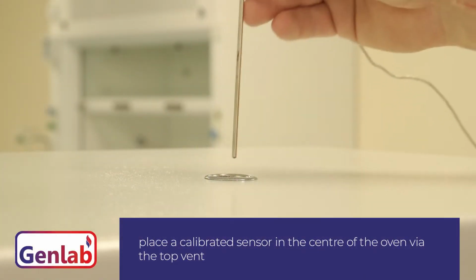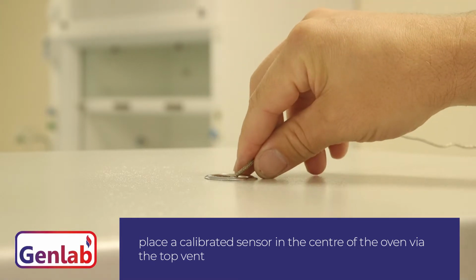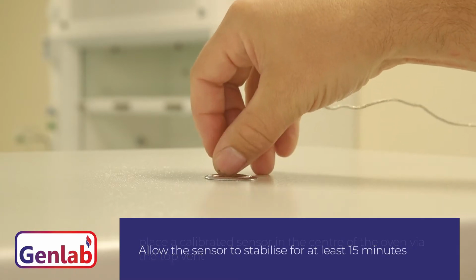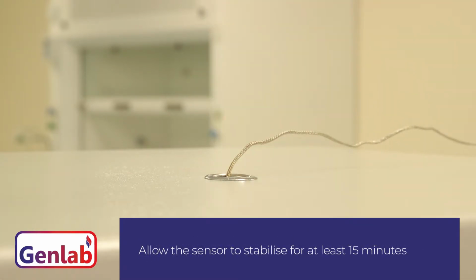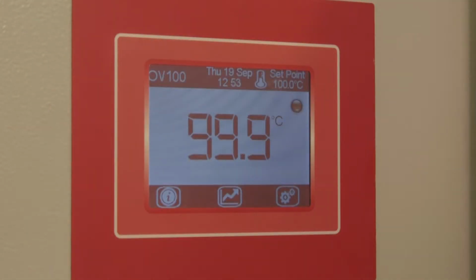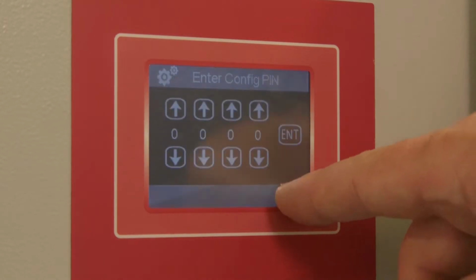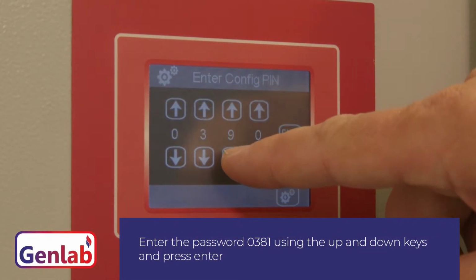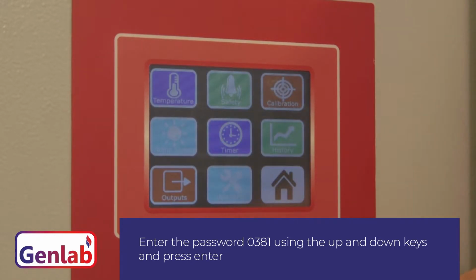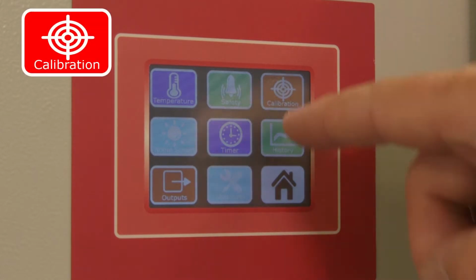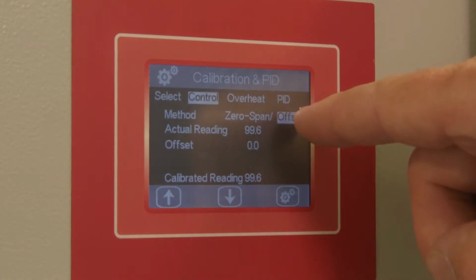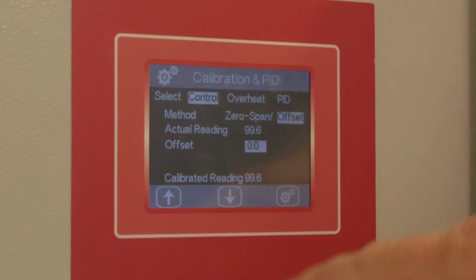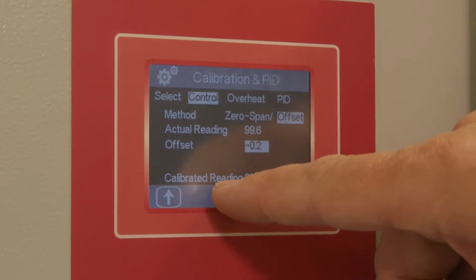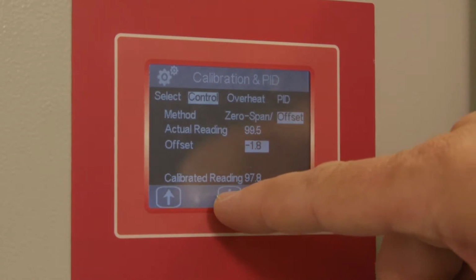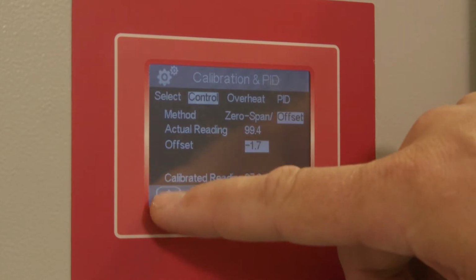Step 1 is to place a calibrated sensor in the center of the oven via the top vent. Allow the sensor to stabilize for at least 15 minutes. To calibrate the oven to this sensor, press configuration icon, enter the password 0381 using the up and down keys, and press enter. Press the calibration and PID section, then highlight the control sensor. Press the offset and then highlight the value. Using the up and down keys, a linear offset is applied and the calibrated value is shown on the lower part of the screen under the Calibrated Reading tab.